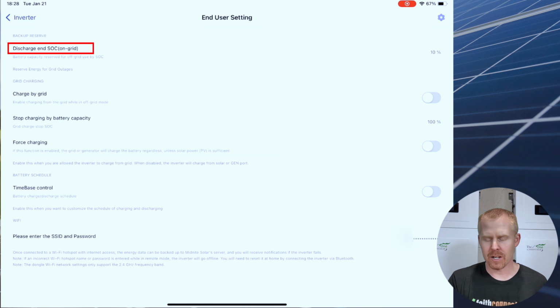You can see right here, it's set to 10% in my system. So when it's in battery mode, discharging from the batteries, it'll discharge down to 10%. And then, assuming you have a grid connection available, it will switch over to the grid. If no grid is available, it's going to keep discharging down until it hits the maximum discharge value set, where it actually shuts the inverter down.